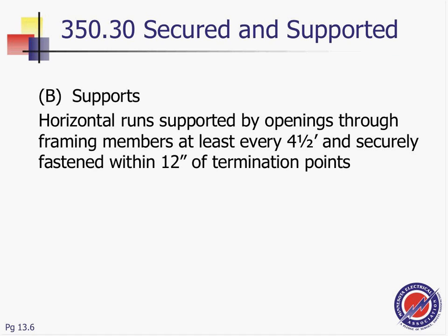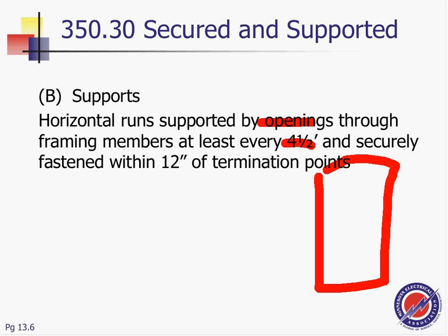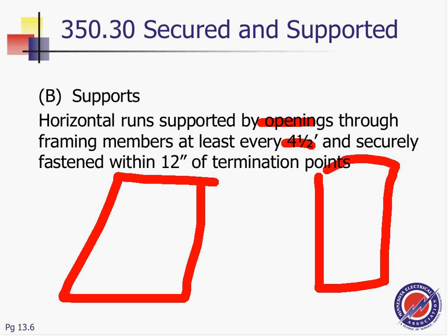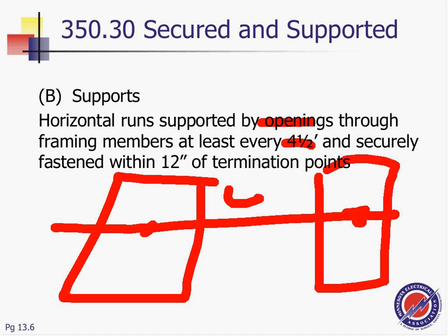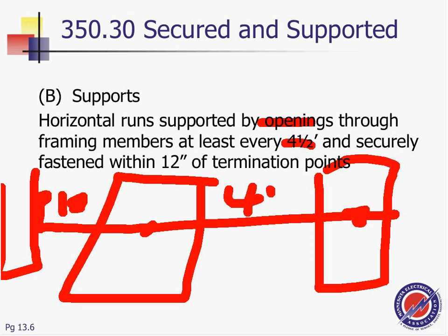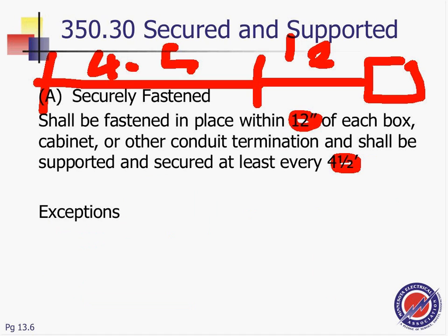If you have an opening, as we said, the studs here and the studs here, and then in between them, go through the holes, no problem. 4 feet. And the last stud, guys, you come over here, you bring your conduit, and you tie 12 inches from the box, and you go. So that fits the hole. The support, back to the support, guys, there's some exceptions for it, exactly like the flex.